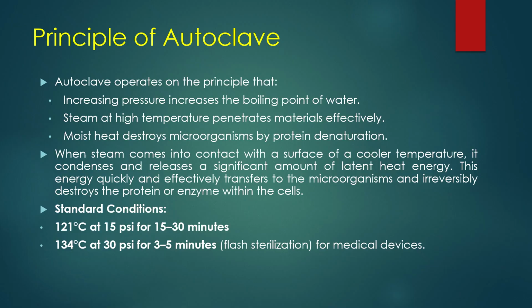Let's understand the principle of autoclave. An autoclave works on the principle of moist heat sterilization, where saturated steam under pressure raises the boiling point of water, allowing high temperature steam to penetrate materials effectively. When steam condenses on cooler surfaces, it releases latent heat that denatures the microbial proteins and enzymes, resulting in the destruction of microorganisms including bacterial spores. Standard sterilization conditions are 121 degrees Celsius at 15 psi for 15 to 30 minutes for standard sterilization cycle and 134 degrees Celsius at 30 psi for 3 to 5 minutes for flash sterilization for medical devices.